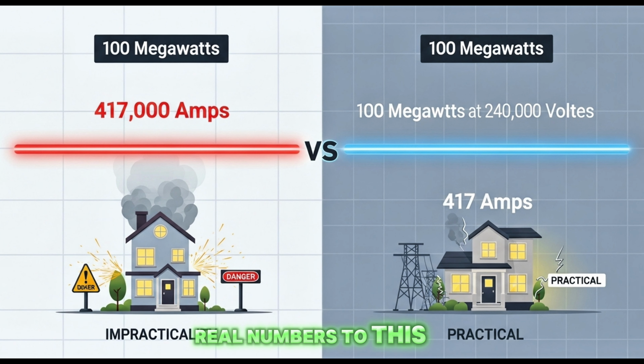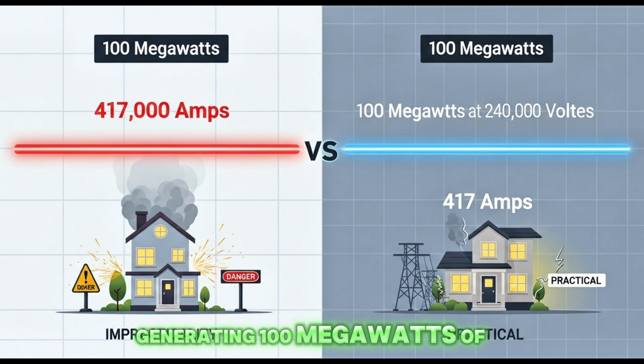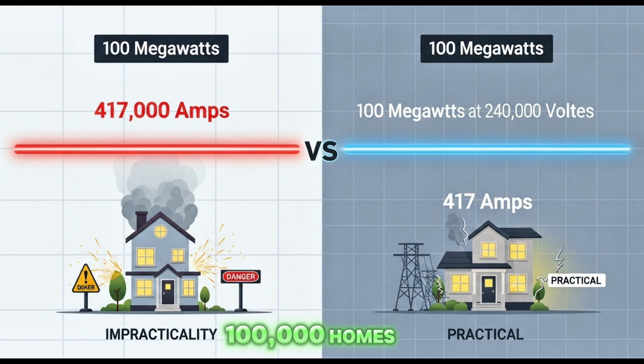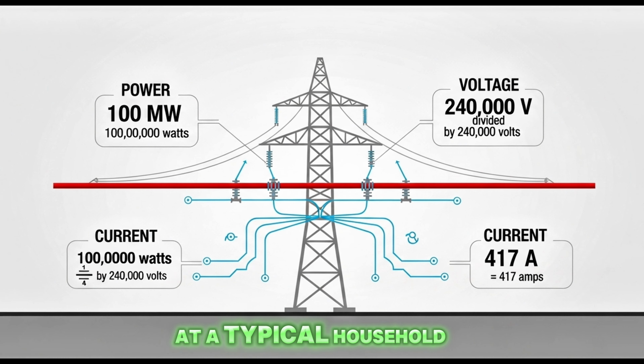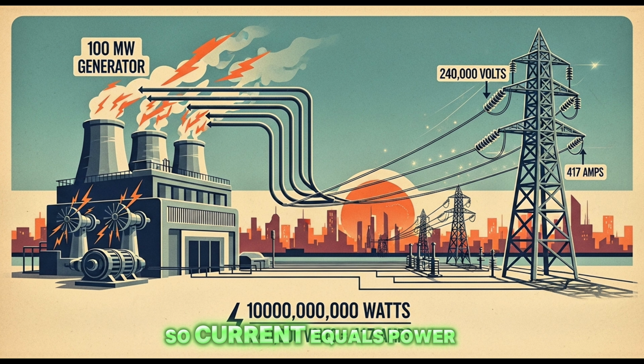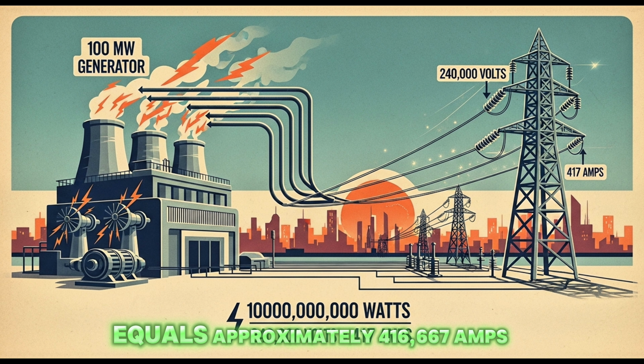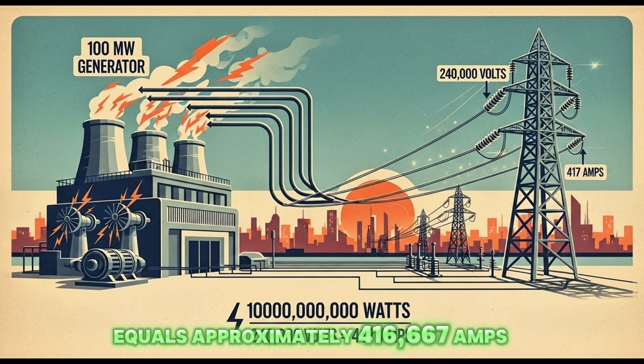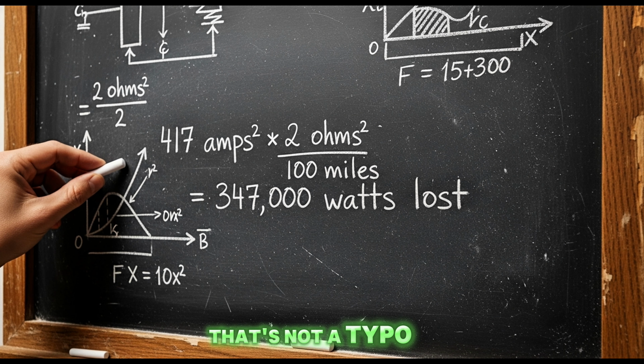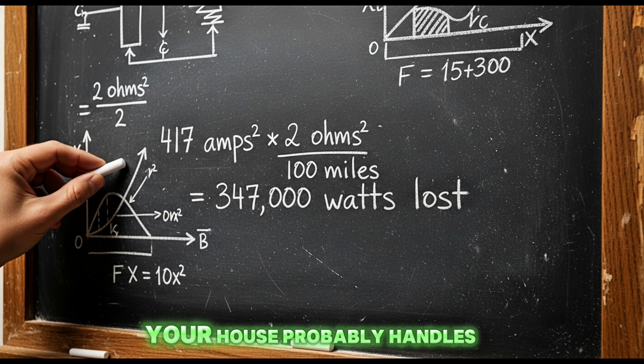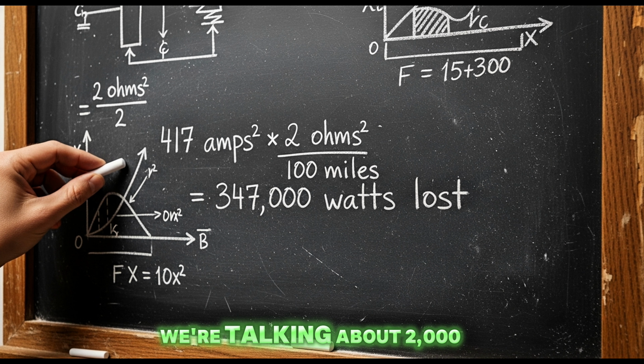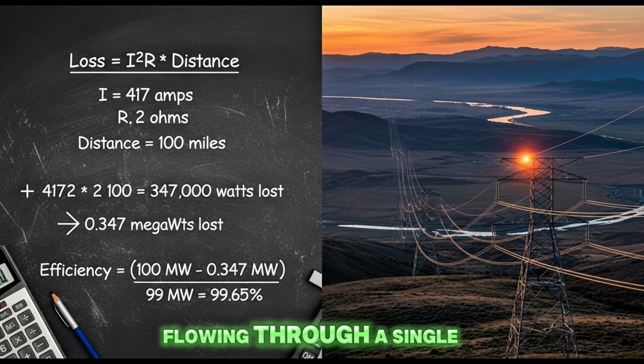Let's put real numbers to this. Imagine a power plant generating 100 megawatts of electricity, enough to power roughly 100,000 homes. If we transmit this at a typical household voltage of 240 volts, we need to calculate the current required. Power equals voltage times current, so current equals power divided by voltage. 100 million watts divided by 240 volts equals approximately 416,667 amps. That's not a typo, 416,000 amps. To put this in perspective, the main breaker in your house probably handles 200 amps. We're talking about 2,000 times that amount flowing through a single transmission line.